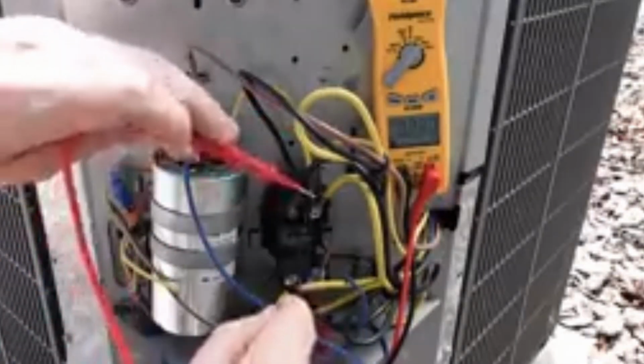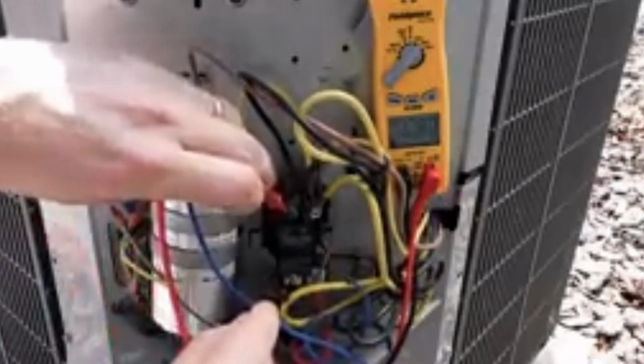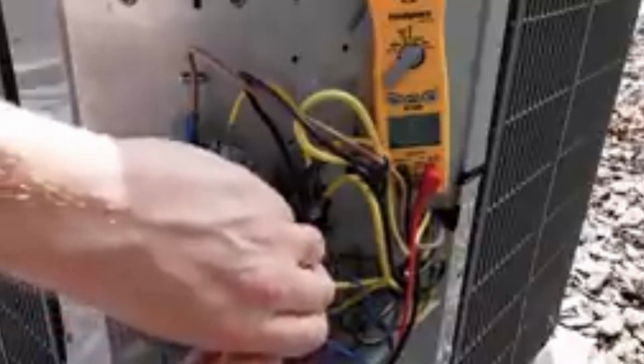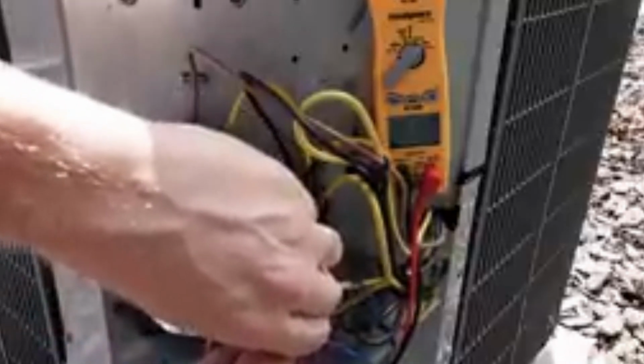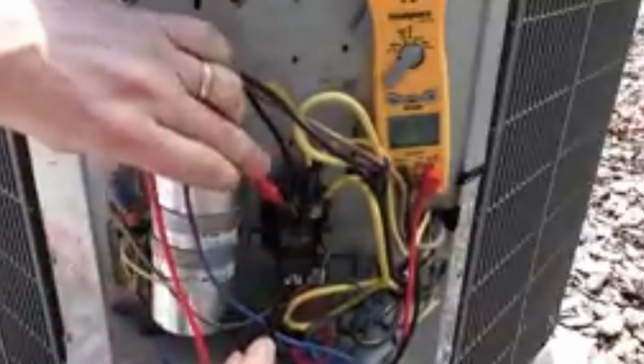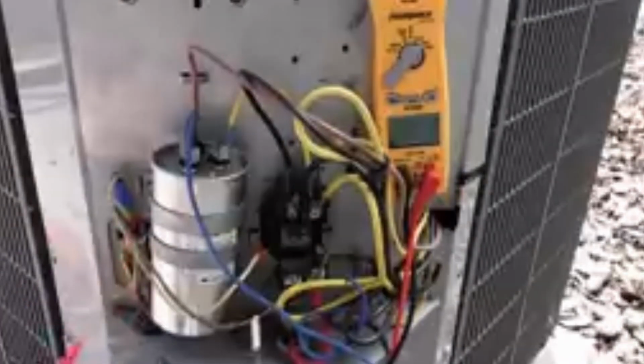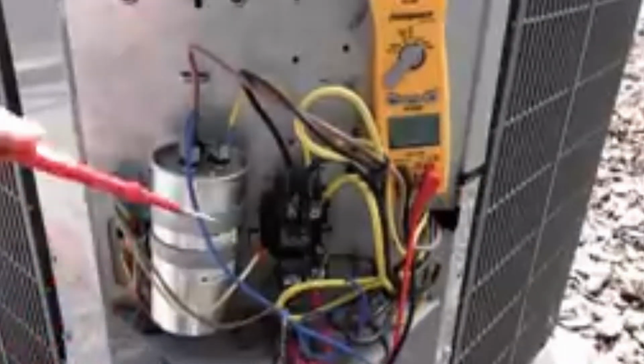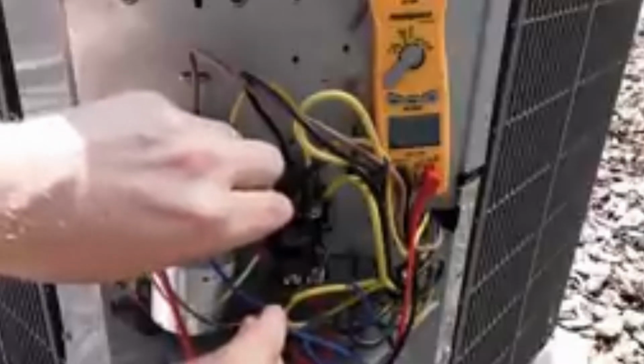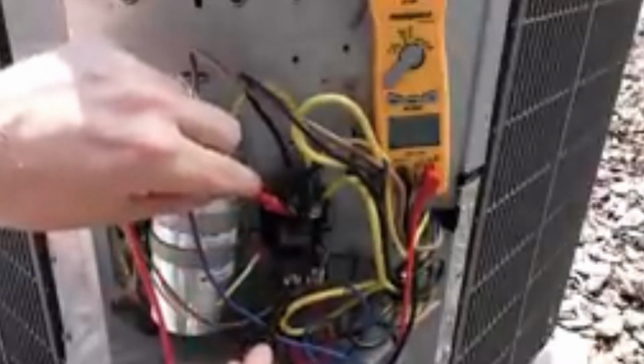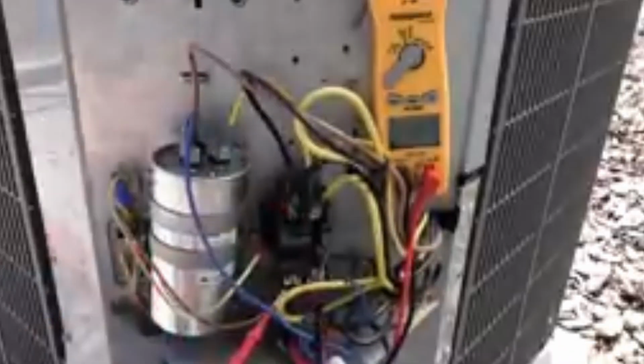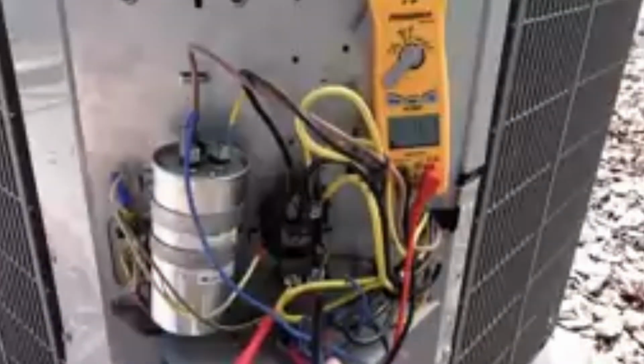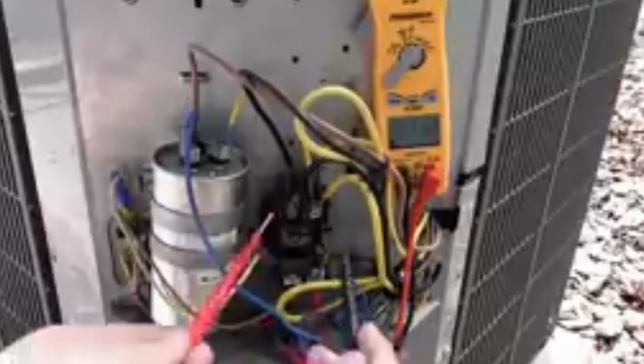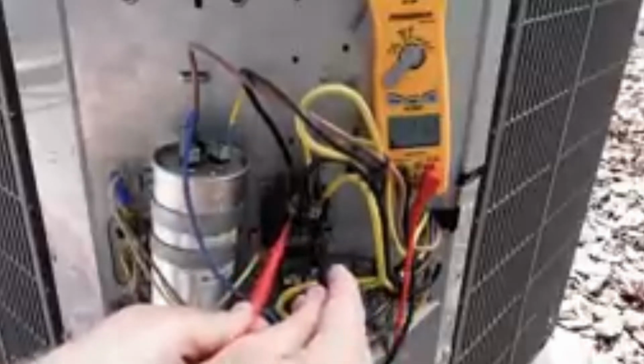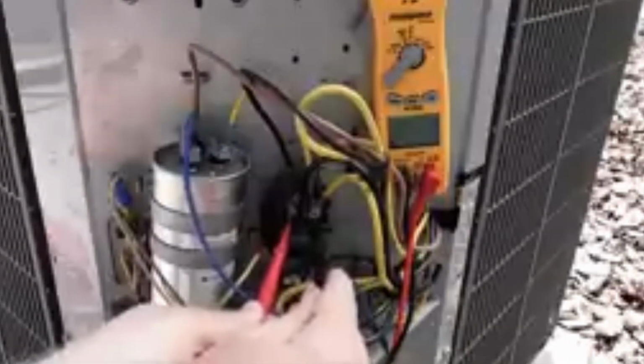Now, because this contact is open, I can measure across it, and there will be a potential difference across these 2 points, where before there was no potential difference. Again, one more time, now you see the contactor is pulled in, and now there's no voltage drop or potential difference across these 2 points. 212 volts coming in, 212 volts going out, which is what you'll show on a running unit.